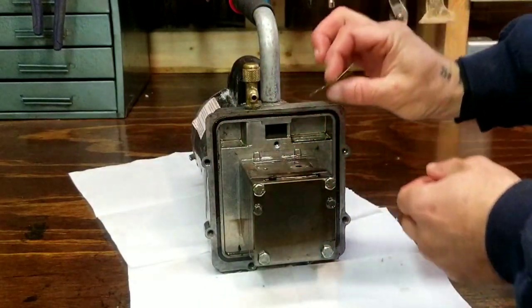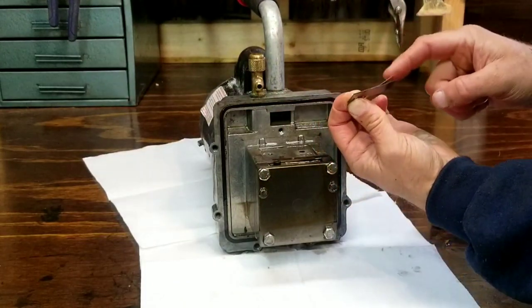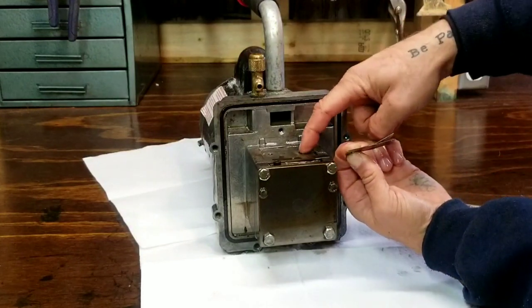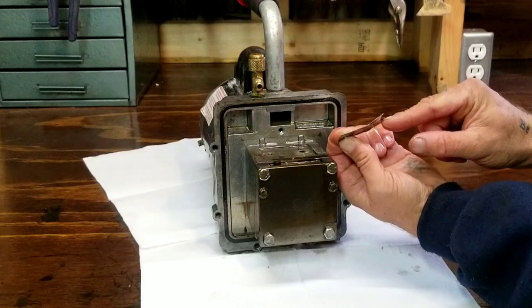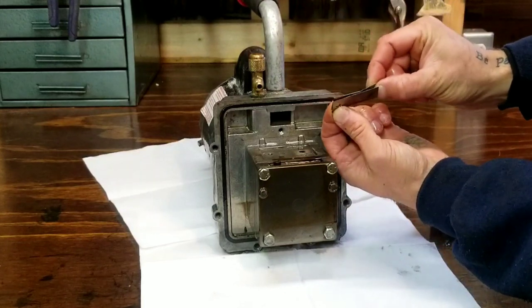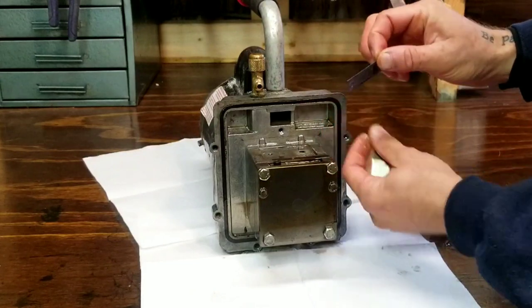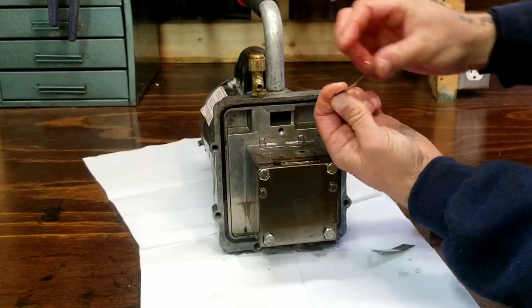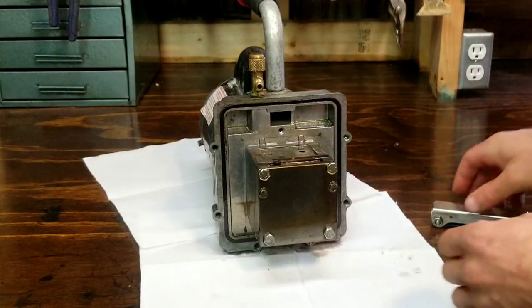So this is our discharge reed right here. Since it has this top piece, I'm assuming this is going to be our discharge reed. What happens is it compresses and pushes the gas or whatever it's sucking out — this little reed will come up. This piece right here is designed to keep it from overextending, from just blowing itself off or bending itself in half. If that wasn't there it would just blow up like that every single time, and eventually it wouldn't work — like it doesn't work now.